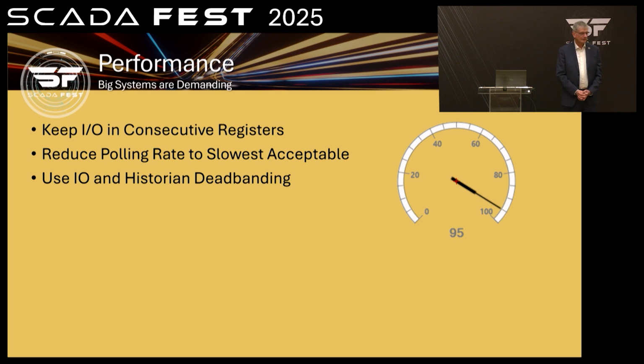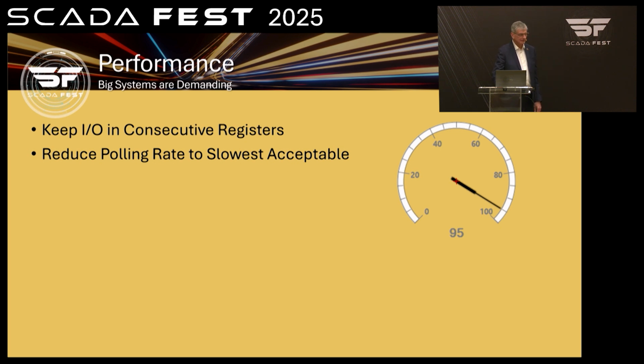And a year from now, you'll say, "Oh, what happened to my disk? I ran out of disk space." So get your dead bands to be something useful, like 1/10%. What can you tolerate? Something fairly tight, but it makes a big difference in how much data moves on. Say, how good are your instruments? Rarely do you find an instrument that's better than 1/10% accurate. But there's always noise on the line. So digital values, not a real problem. They're on or off, and you want to record every single one of them. They change so rarely that it's not a dead banding issue at all.